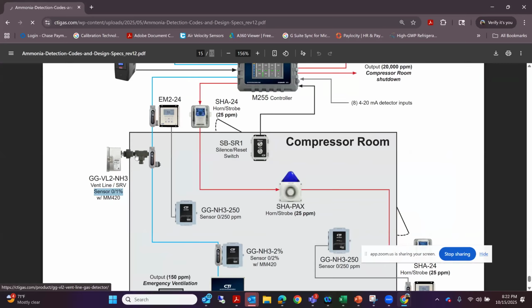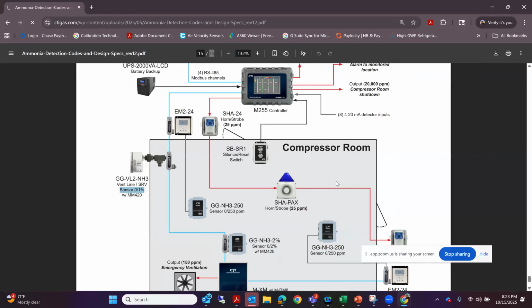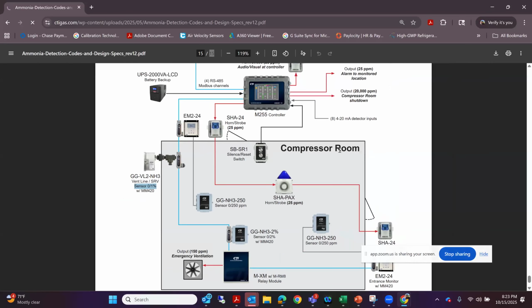Let's go ahead and tell those guys to shelter in place for a moment before running out of the building, because that ammonia alarm is outside while some of these other ones might be inside. And so you don't want to run everybody outside if it's this one that's going off, whereas if it's a high level compressor room leak, then maybe it makes sense to get everybody heading out the door in the opposite direction of the compressor room. But do you guys have any questions on that so far?